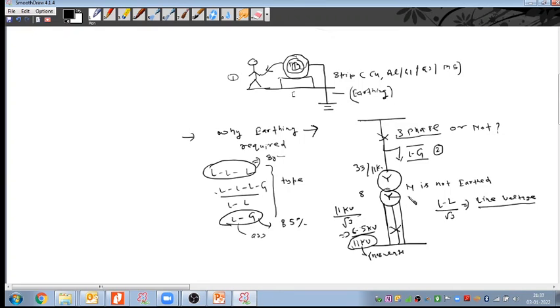If we do the earthing of this star point to the ground, then this earthing provides a return path. This fault current, whatever is coming, because the ground is common, will go back reverse here. Now what I will do, I'll put the CT here that we refer to as the NCT, neutral current transformer.